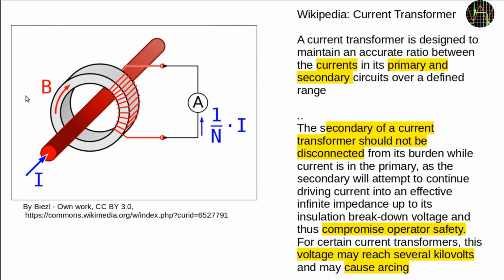For one, as you can see from the formula, the more windings N the coil has, the lower the current measured by the ammeter. If, for example, the current through the thick wire going through the coil was 1 amp and the coil had 100 windings, then we measure 1/100th of an amp or 10 milliamps. If we use a coil with 1000 windings, we only get 1 milliamp, quite the opposite of a voltage transformer where you get higher voltages the more windings you use.